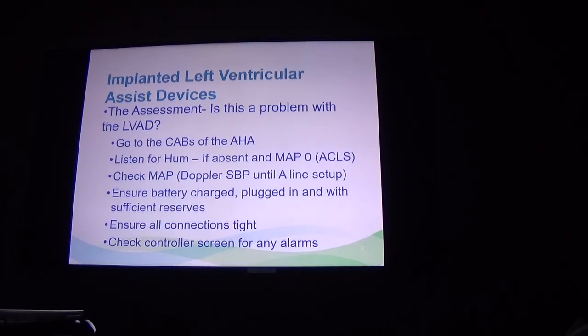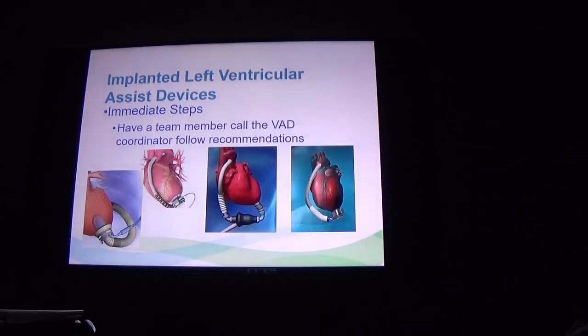Make sure the battery's charged and plugged in and ensure connections are tight. The connections being tight is kind of a theme of any VAD or assist device. And then again, check your controller screen for any alarms. So here are just some of the different models of LVADs, but your first step should be to assign one of the members of your team or whoever to call the LVAD coordinator. Even if it's 2 in the morning, and they're like the Medtronic reps and take 20, 30 minutes to get back to you, you're still going to have that heads up by getting someone on board quickly.